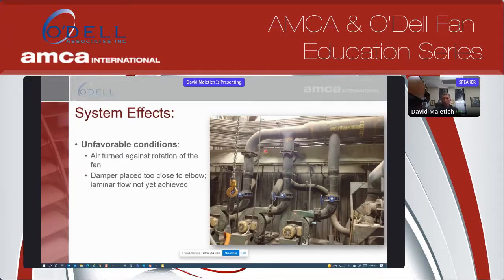Low combustion air system, high pressure fans. Again, you have these elbows, position C elbows. Air wants to go around here, deadheads against the back, has to get reaccelerated out. They have these wafer dampers, which are vertical. A lot of times people think guide vanes improve flow. Guide vanes can actually hurt flow as well if they're improperly located. So this damper going vertical means that the air is going to come in at this high velocity. It's going to enter the one side of the damper. So you're going to have a high velocity side of the damper and a low velocity side of the damper. And that's going to extend the non-uniform profile of air discharging this damper system much higher than if they were to put the damper higher up in the system or right at the discharge of the fan.